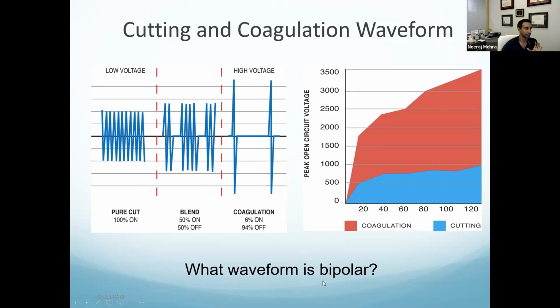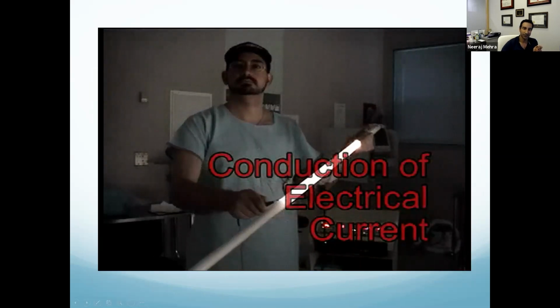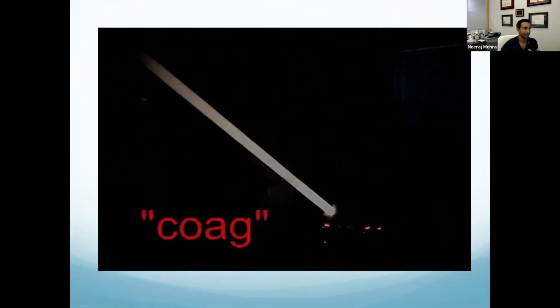Does anyone know what waveform bipolar is? If I want to take a guess. So bipolar mode, if you use that, is the same as the cutting mode. So it's the one that's on all the time. It's a constant mode. Now, hopefully this works. There we go. So this is just showing you a visual example of what this is. So this is the cut mode. And you'll see the coag here. So with the cut, it's the slow amount of energy over time, and with the coagulation mode, the high voltage, that energy just surges through.